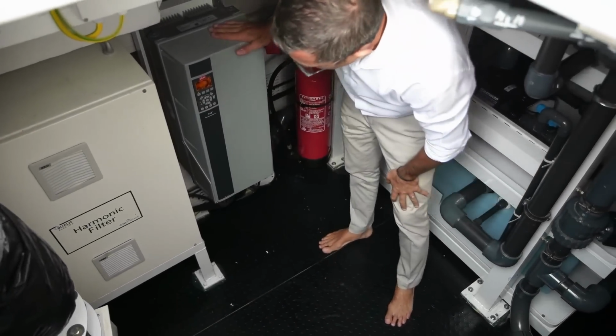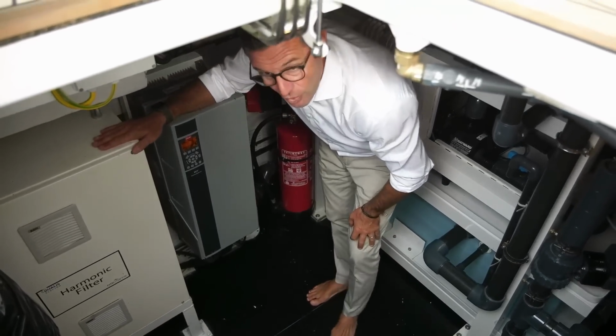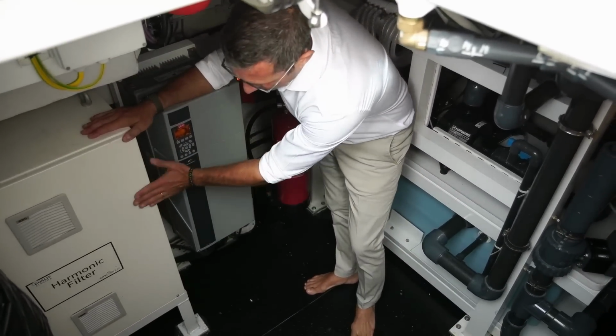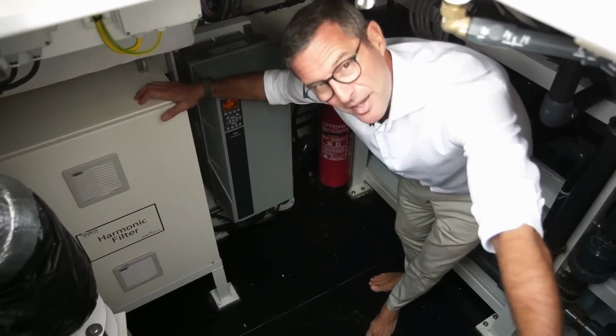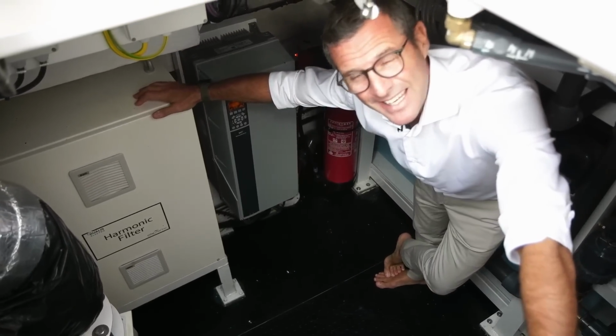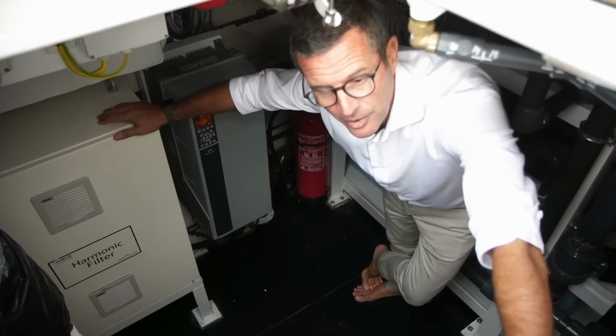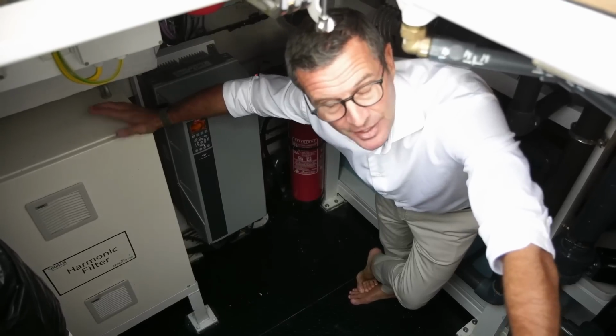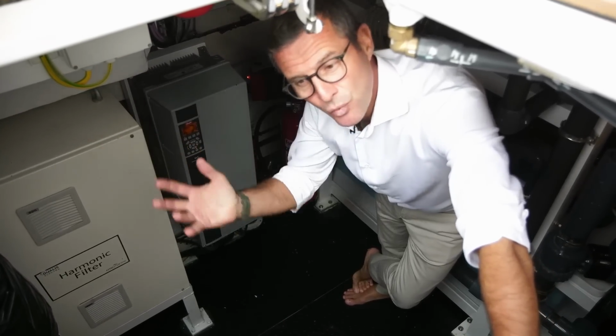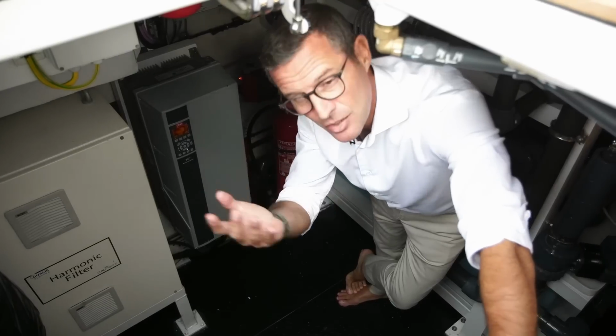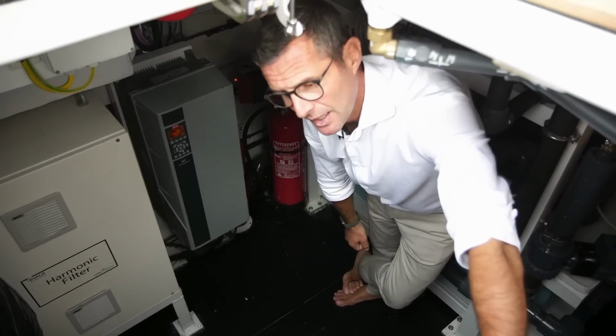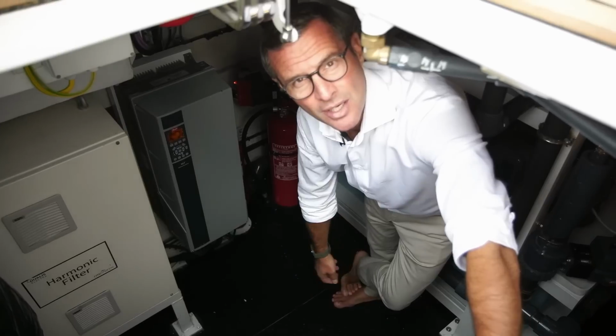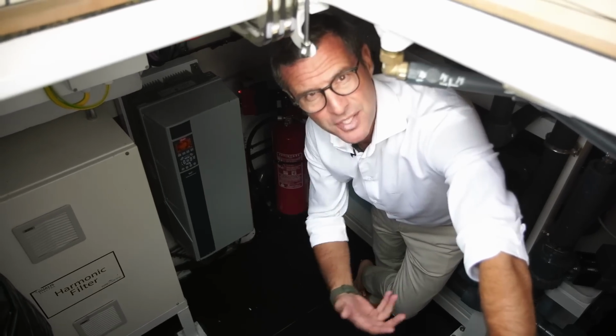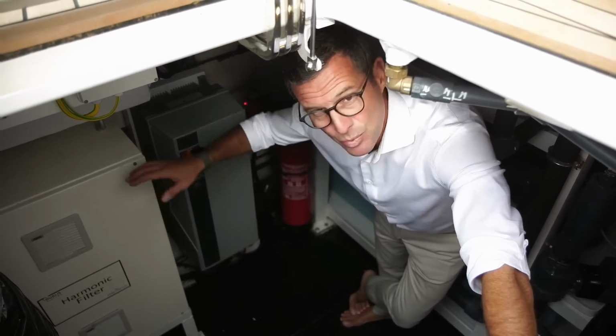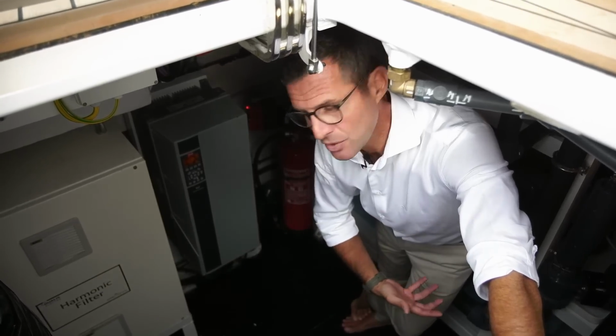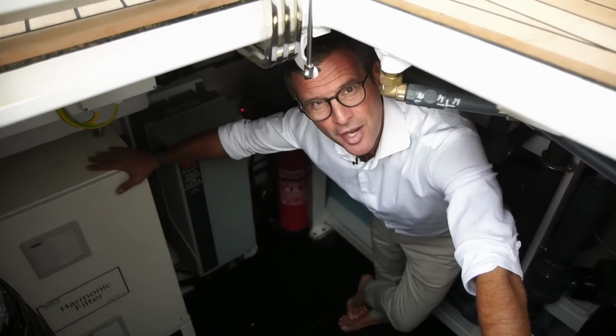So here is interesting. First of all, these two beauties right here. We discussed the bow thruster before, which is 70 kW. That creates strong harmonic currents which would disturb the rest of the electrical components on board. You want very low harmonic disturbances on the electrical line as you can, so equipment this powerful requires a harmonic filter.